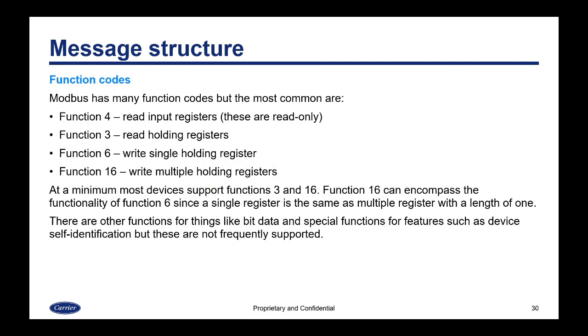Modbus has function codes to transmit data. The most common are: Function 4, which is a request to read input registers (read-only registers); Function 3, which is to read holding registers; Function 6, which is to write a single holding register; and Function 16, which is to write multiple holding registers. At a minimum, most devices will support Functions 3 and 16. Function 16 can encompass the functionality of Function 6 since a single register is the same as multiple registers with a length of 1. There are other functions for bit data and special functions like device self-identification, but these are not frequently supported.